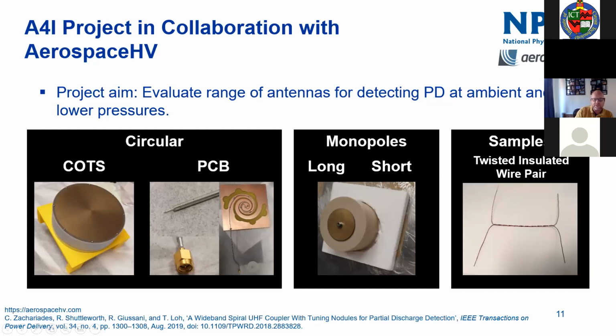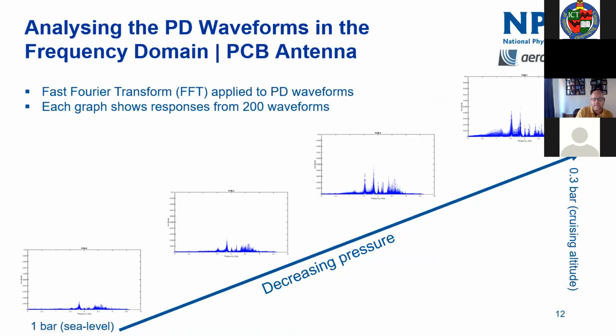Our test vehicle, the one we've done most of our work on so far, is this twisted wire pair, which represents the windings inside a motor core. That project showed us there was definitely a change in the PD occurring as we reduce pressure. These show the antenna waveforms - the signal the antenna is picking up, so not directly associated with voltages - but you can see the energy of these PD discharges clearly increasing as we decrease the pressure. We went down in this case to about 0.3 bar, which is a typical civilian aerospace cruising altitude.